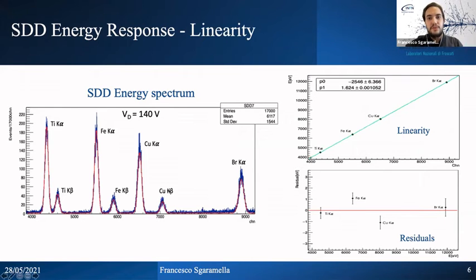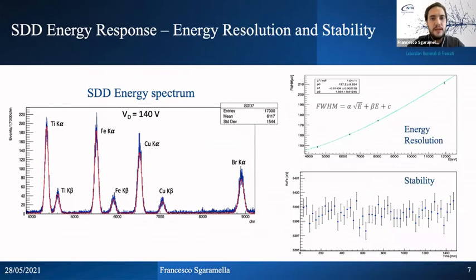So the Gaussian peak position and width have been extracted from the fit parameters to calculate, first of all, the linearity. And about the linearity, only the K alpha peaks have been used, since they have a higher signal to background ratio with respect to the K beta peaks. The slope of the linear function corresponds to the gain of the system in terms of electronvolts over channels. Also, the residuals have been calculated to evaluate the linearity of our system. Here I report the energy resolution and the calibrated position of the K alpha iron peak during the stability run.